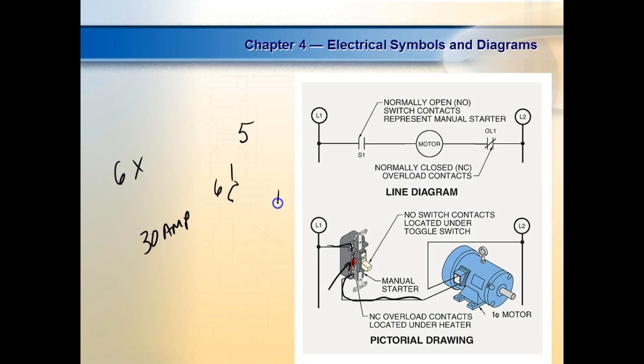So this is the symbol for an overload sensor. It's got these hook shapes, they should touch. This is not the overload, this is the sensor that senses the overload. Now what we do in the control diagram is we put that over there. So these sensors trip this thing right here. When there's an overload, it opens that contact right there, and if that opens, then you lose L2. You have to have L1 and L2 for it to run, right? You understand that? So that's the symbol of the contact controlled by the overload sensor that's out here on the motor.